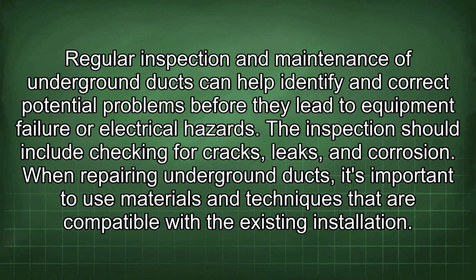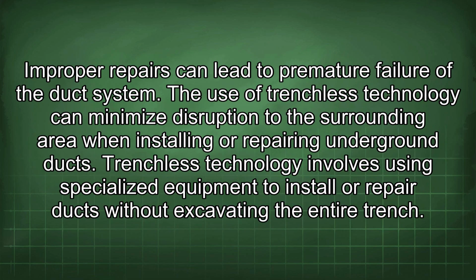When repairing underground ducts, it's important to use materials and techniques that are compatible with the existing installation. Improper repairs can lead to premature failure of the duct system. The use of trenchless technology can minimize disruption to the surrounding area when installing or repairing underground ducts. Trenchless technology involves using specialized equipment to install or repair ducts without excavating the entire trench.